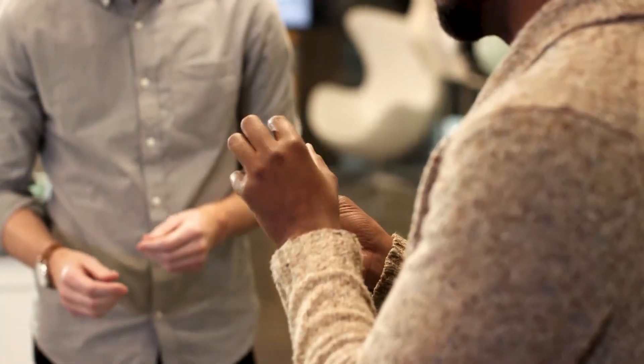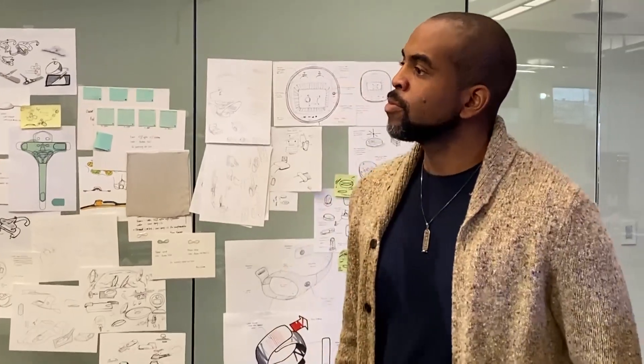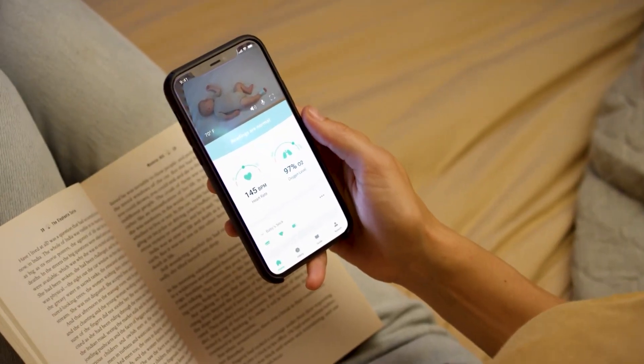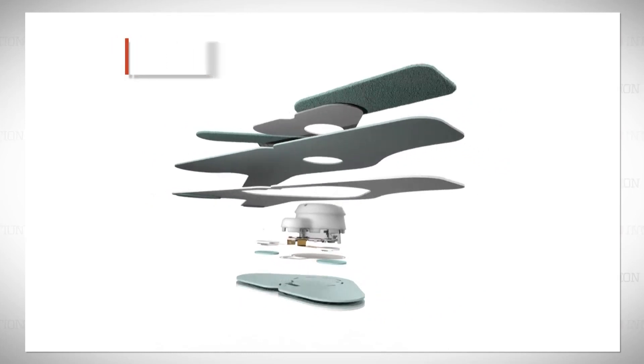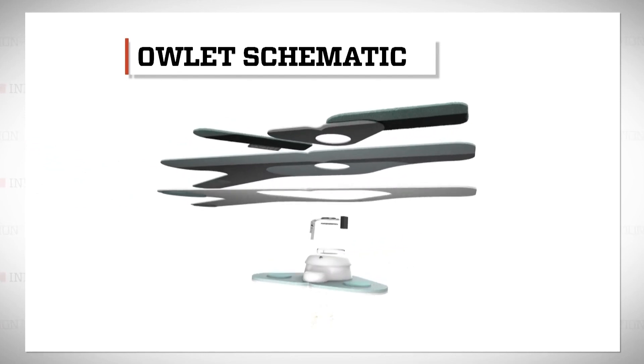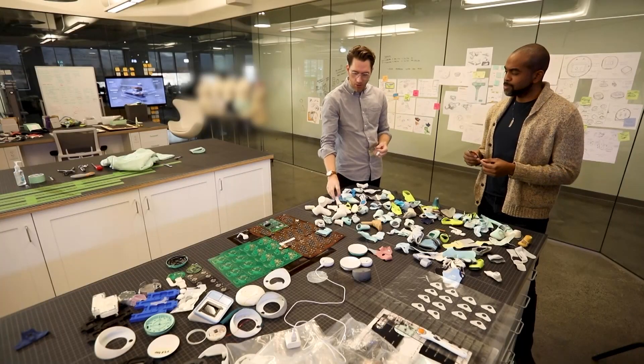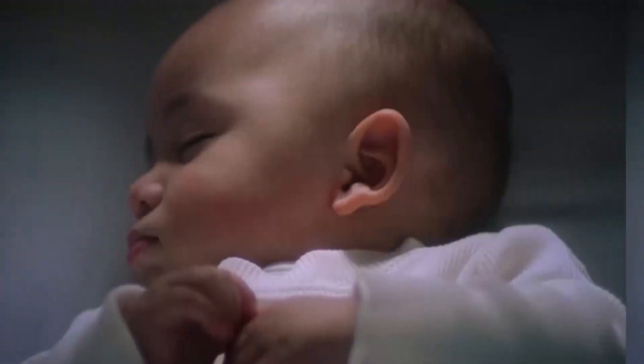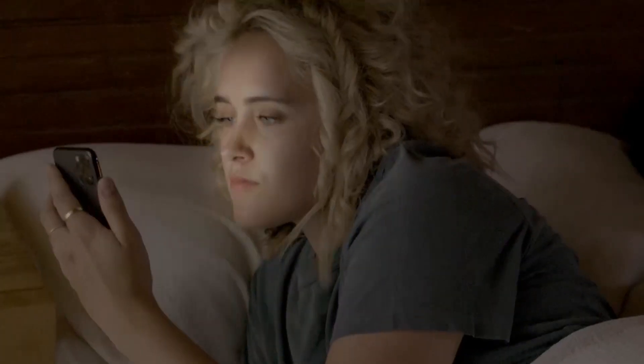What's doing all the work within this? We have a microcontroller, and this is where the battery, the Bluetooth antennas, and the LED and photodiodes are. It can see what's happening inside the blood — that's how it reads how much oxygen is actually in the blood, and that's also how you read heart rate. We're taking that Pulse Ox technology, scaling it down, and making it wireless, which is one of the bigger challenges — taking something that is currently large and scaling it down to fit on a foot this small and be wireless has been the biggest challenge for us to figure out. The Smart Sock is usable on babies from five up to 30 pounds.